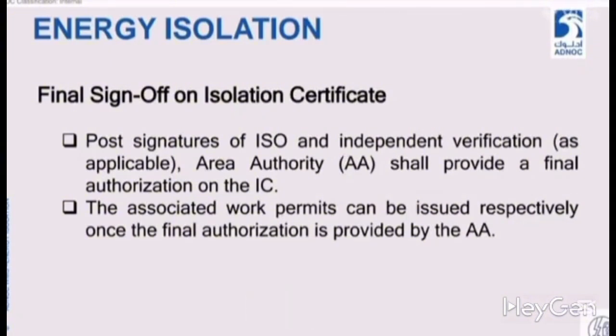Until our ICCs are approved, they will not be live, and their associated permit cannot be live in the system as per WS. So we must follow all these steps to make the permit live. The ISR will indicate the isolation point. The ISO will perform the isolation. The ISO must demonstrate zero energy to the JP. The ICC will be signed. The AA will approve the ICC. Only then will it be linked with the permit. The permit will be live, can be approved, and we will be able to start work with it.